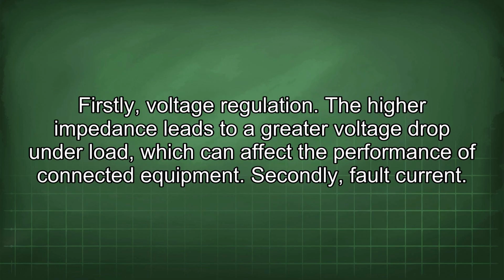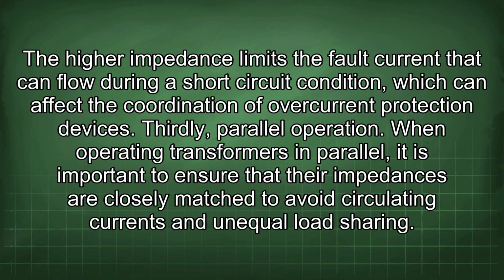Firstly, voltage regulation. A higher impedance leads to a greater voltage drop under load, which can affect the performance of connected equipment. Secondly, fault current. The higher impedance limits the fault current that can flow during a short circuit condition, which can affect the coordination of overcurrent protection devices. Thirdly, parallel operation. When operating transformers in parallel, it is important to ensure that the impedances are closely matched to avoid circulating currents and unequal load sharing.